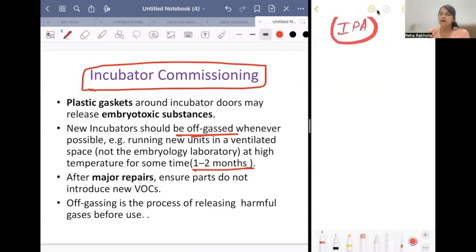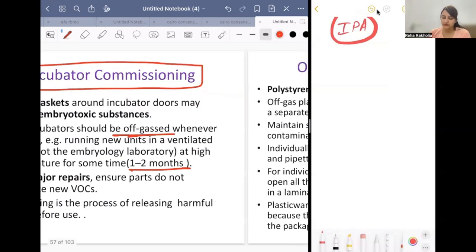We have to switch on the incubator, keep the temperature high, and leave it like that so that off-gassing takes place and any toxic VOCs evaporate. After a major repair, ensure the parts do not introduce new VOCs. After repairing, make sure that whatever parts they use do not introduce any new VOCs into the laboratory. Off-gassing is the process of releasing harmful gases before use.